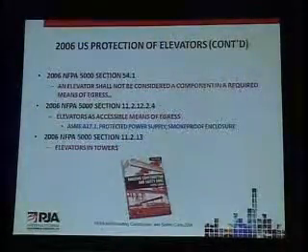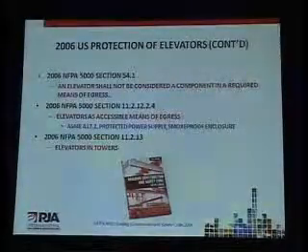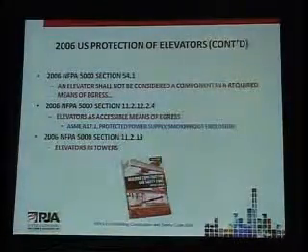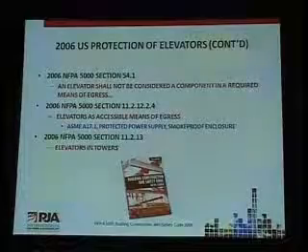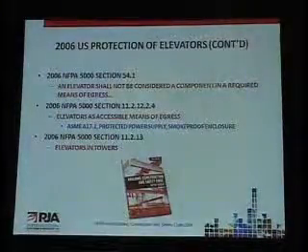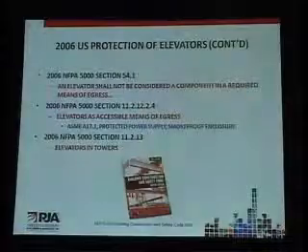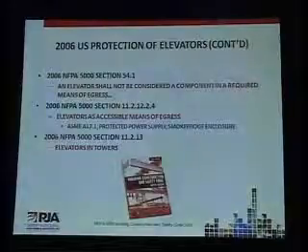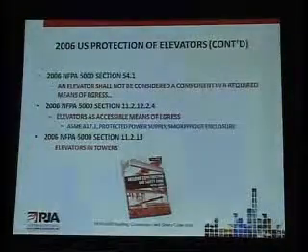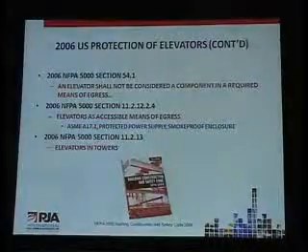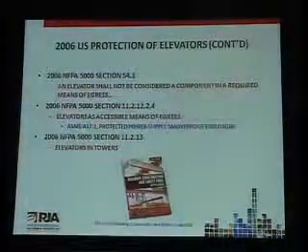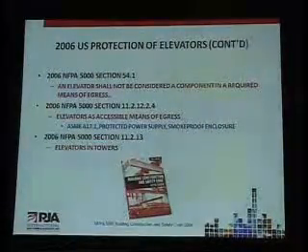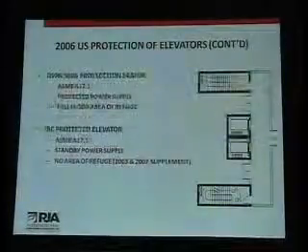NFPA 5000 is widely used throughout the Middle East, so that's why I included it in this. But essentially, the requirements are very, very similar to the IBC, which is predominantly used in the United States. Again, they do have exceptions for elevators to be used for handicap occupants, but they also include provisions for elevators to be used in towers, primarily air traffic control towers, where you have a very skinny base that comes up into a much larger area for the occupancy of all the equipment and the air traffic controllers. So there you're allowed to eliminate a stair if you can provide protected elevators.